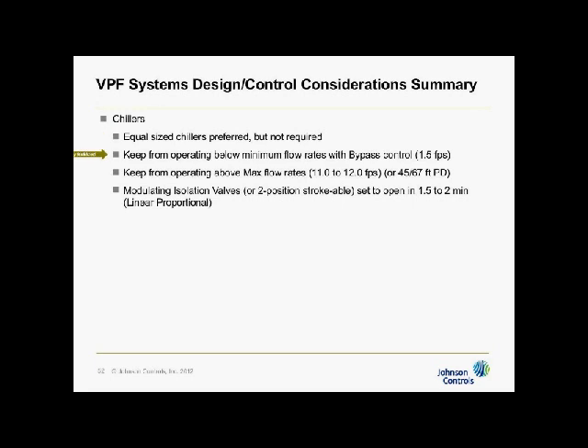You have to keep operating to stay within minimum flow. So you can't go below 1.5 feet per second. Every chiller manufacturer has GPMs they can give you for that. So you have to maintain flow above that, which is why we use the bypass valve. And you can't go above max flow rate or you'll destroy the tubes. You'll wear them right out. And that's usually 11 to 12 feet per second, as I said earlier. And it's 45 or 67 feet of pressure drop, depending upon whether it's a 2 or 3 pass shell.